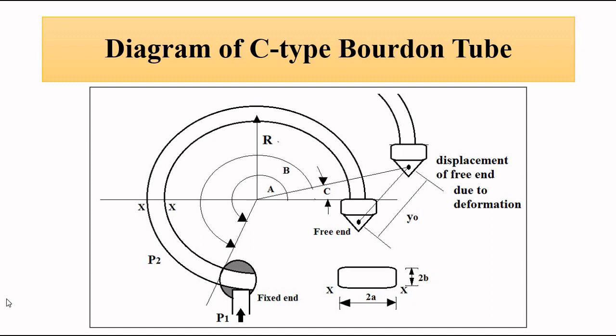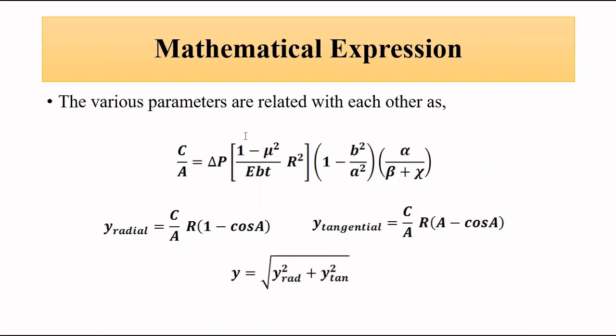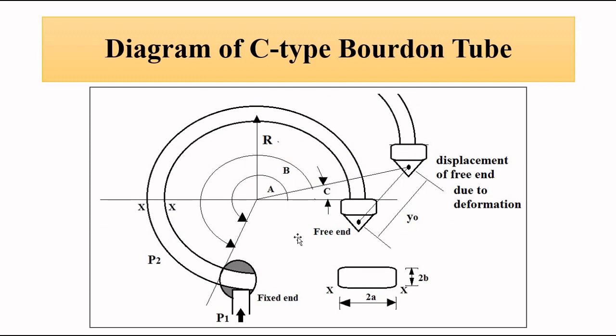So the mathematical relationship between the displacement of the free end and the differential pressure is given by this relationship. This equation can be a bit complicated, a bit tricky, but try to understand this. The important thing to note here is first the angle A, the initial position of the Bourdon tube where no pressure is applied.